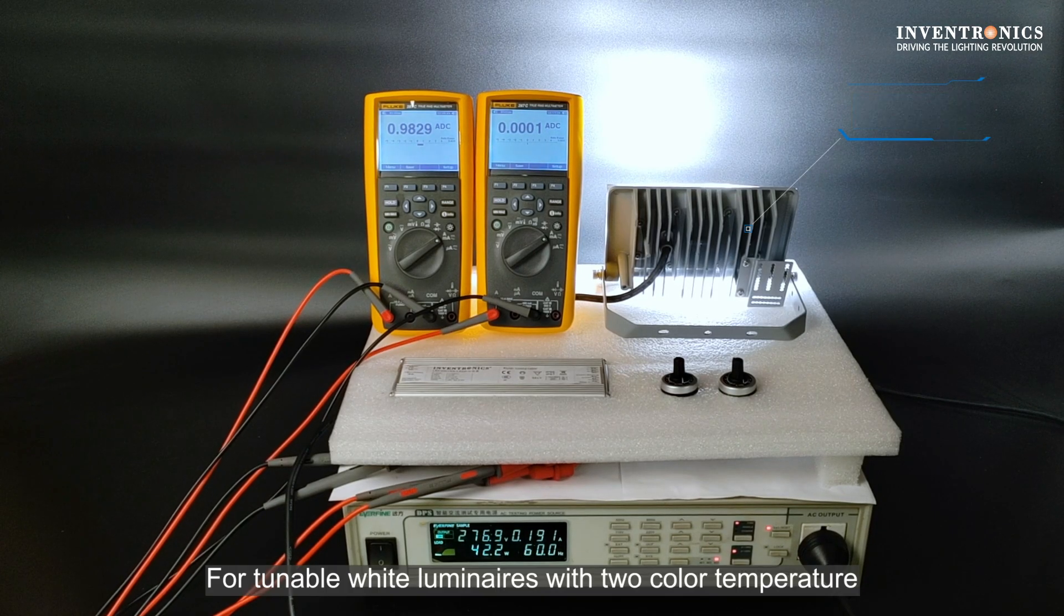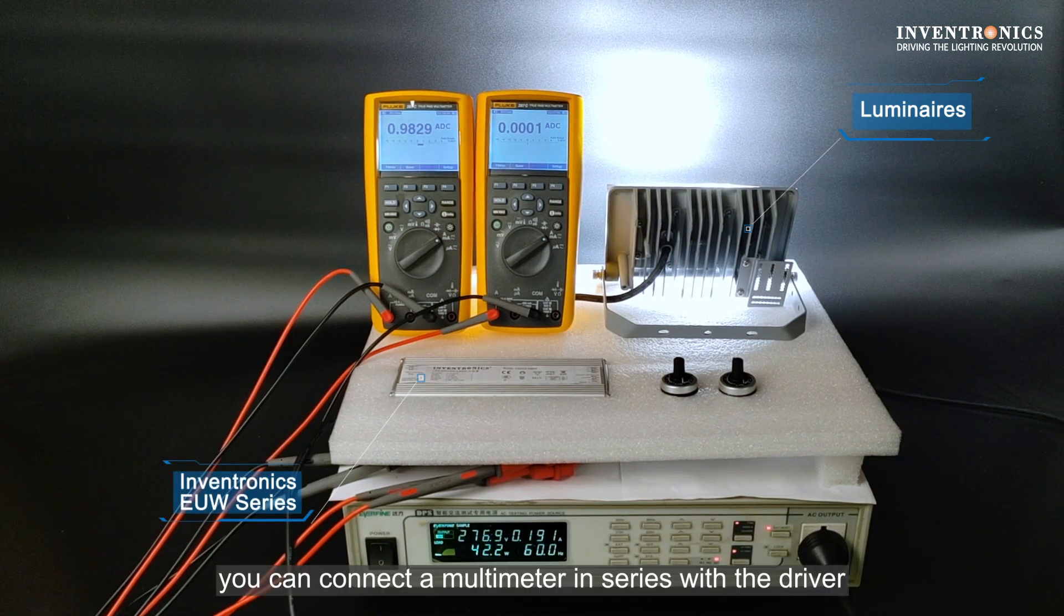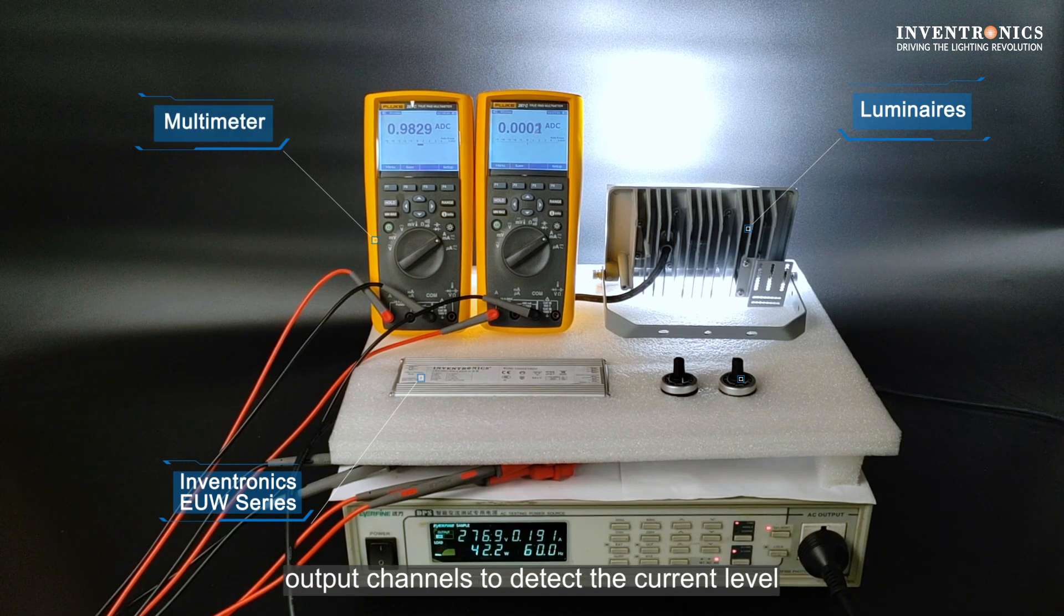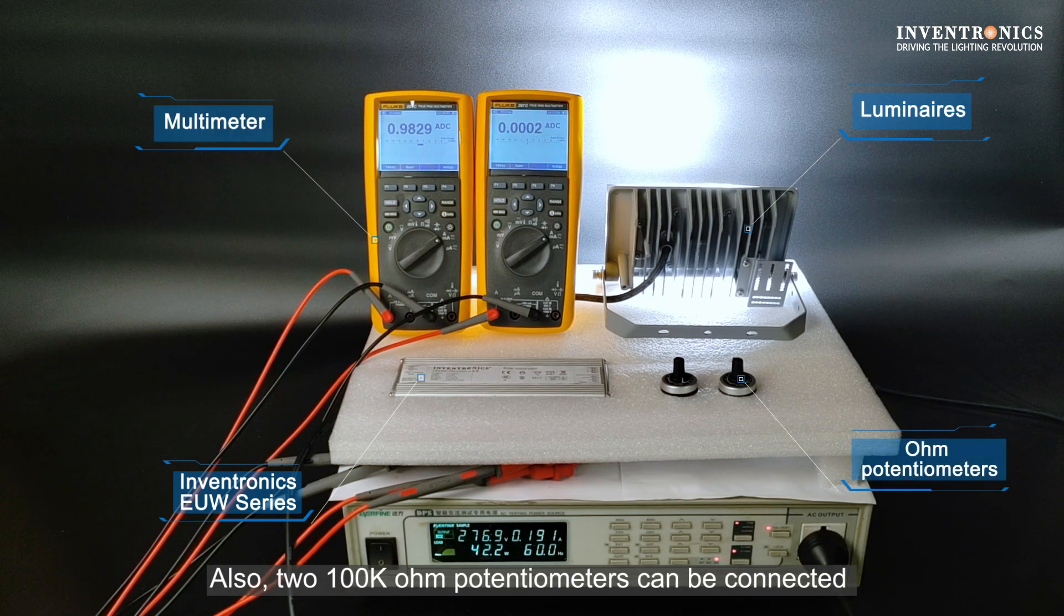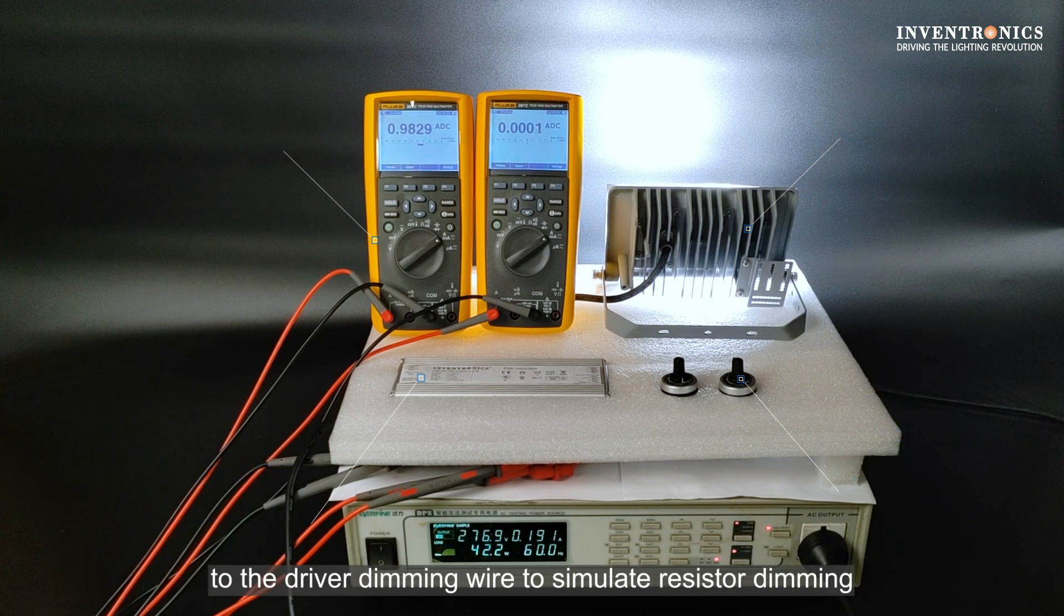For tunable white luminaires with two color temperature channels of 3000k and 6000k, you can connect a multimeter in series with the driver output channels to detect the current level. Also, two 100k ohm potentiometers can be connected to the driver dimming wire to simulate resistor dimming.